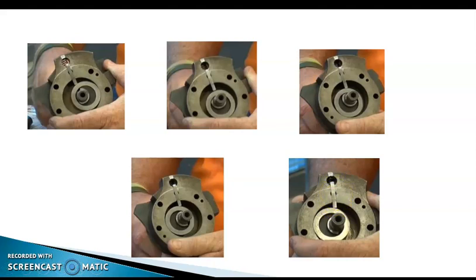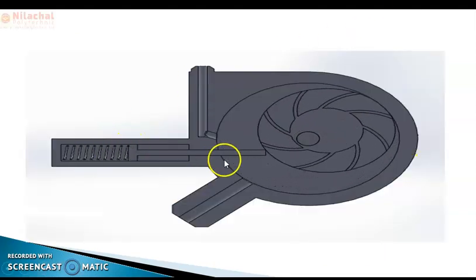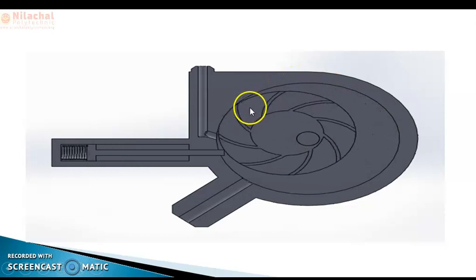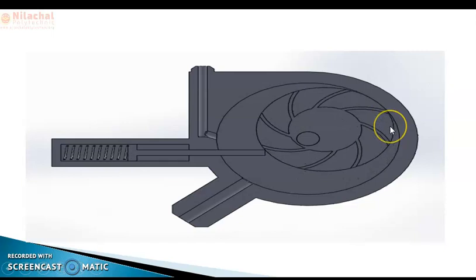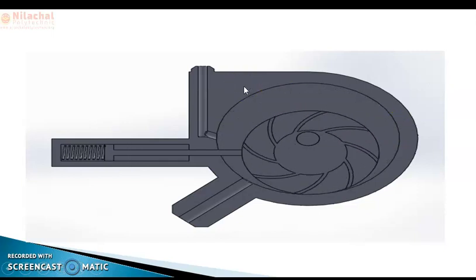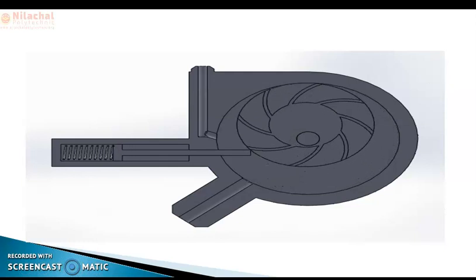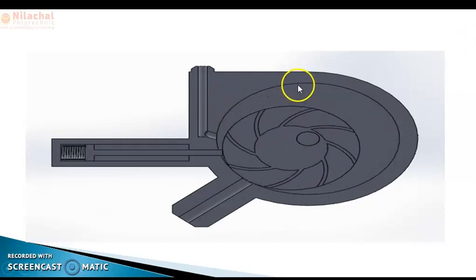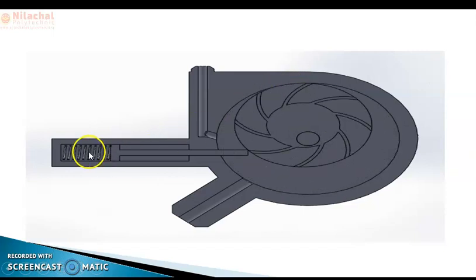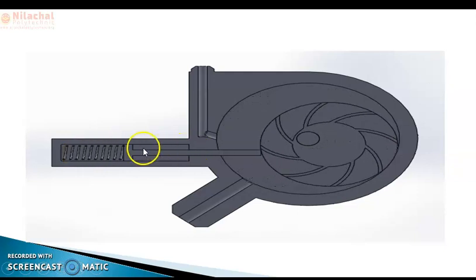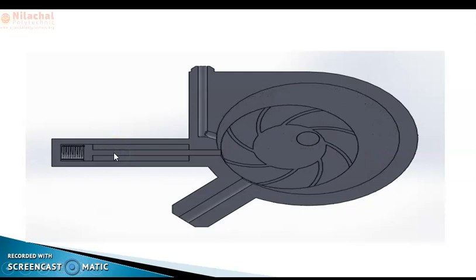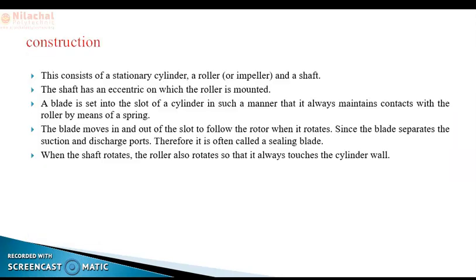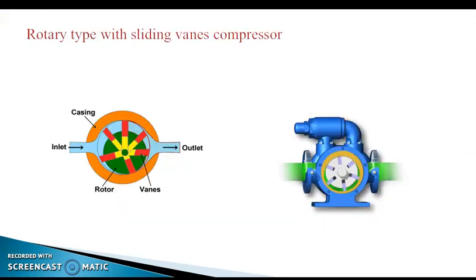In the animation video you can observe the roller moving eccentrically inside the cylinder wall — sometimes nearer, sometimes farther away. When it is nearer to the cylinder wall it is compressing, and when it is farther away it is performing suction. So suction and compression happen simultaneously, making it a continuous process. The spring compresses when the roller is nearer to the cylinder and expands when it is farther away. This concludes the explanation of the single stationary blade type rotary compressor. Thank you.